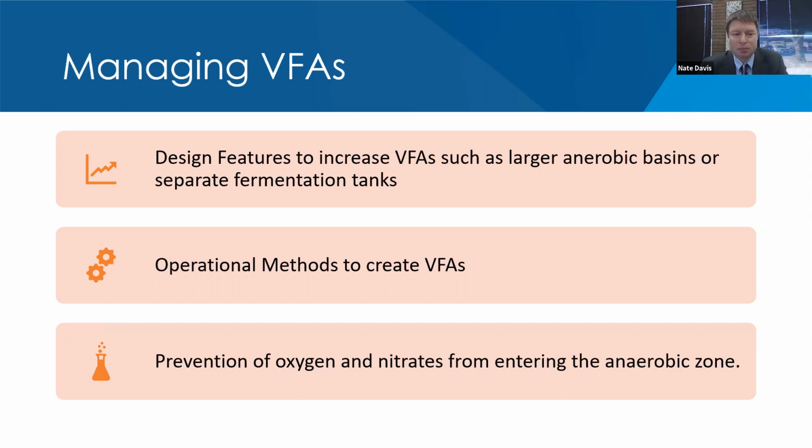So, you know, some culprits to look out for would be like screw pumps, or excess falls over weirs, or just really high zones of turbulence in channels or something that can entrain oxygen. Aerated grit chambers could be another one. And nitrates may not always be coming from internal to your plant too.